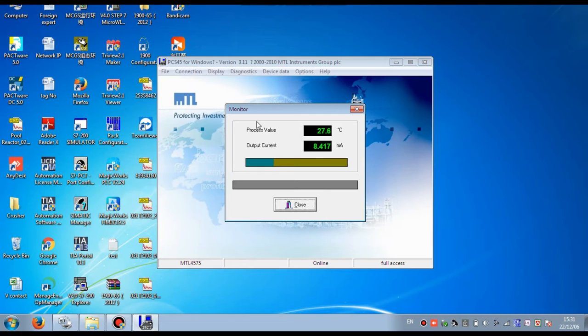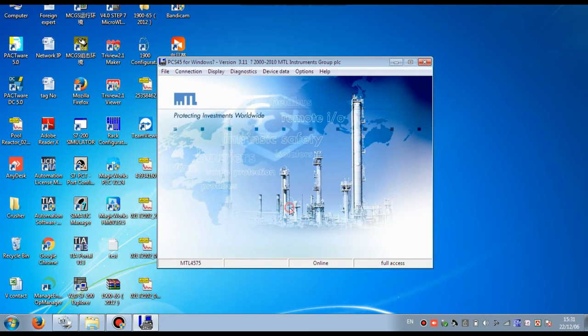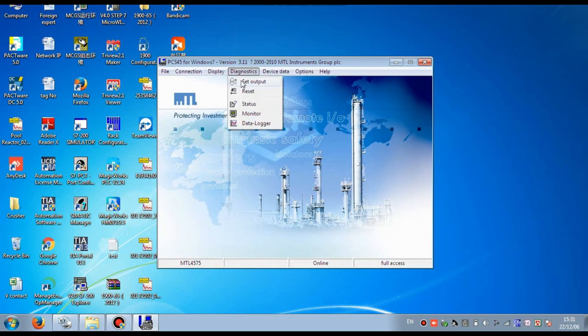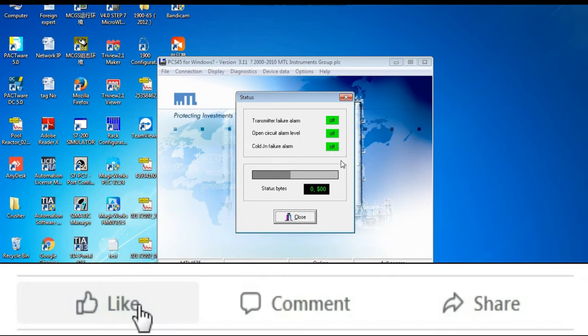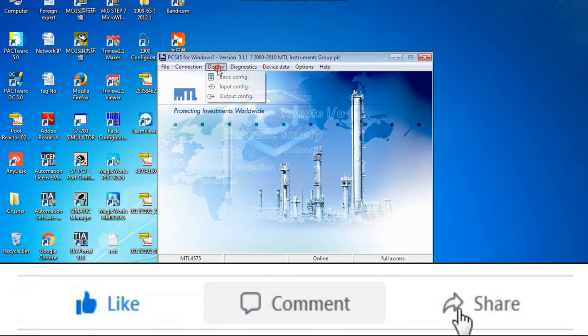Now I will show you whether the setting parameters are correct. Go to Diagnostic and then to Status. Here you can see the transmitter status: transmitter failure is off, open circuit alarm is off, cold junction sensor is off — that means our sensor is 100 percent okay. Then press Close.